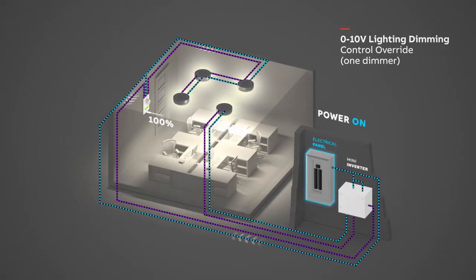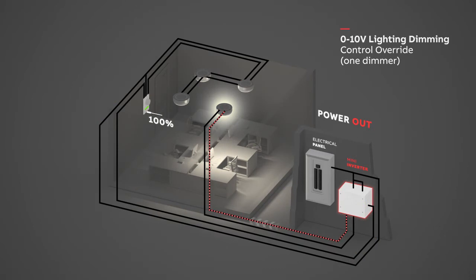When the main power goes out, the Mini Inverter LCO will bypass the dimmer so that even if the dimmer is off or down, the lights wired as emergency lighting will turn on at full brightness powered by the Mini Inverter.